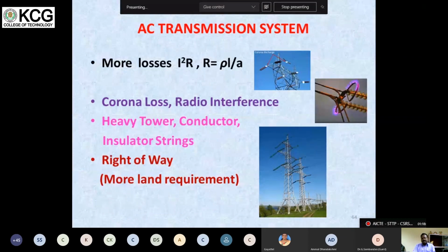Okay, AC transmission lines have some problems, like more losses. They have I squared R loss, resistance loss, and inductance loss also. I squared R is a power loss. Whatever power is generated, when it reaches the load center it incurs losses: technical loss and commercial loss. Technical loss is I squared R loss. R is rho L by A. The loss increases with the resistivity of the conductor, and it also increases with the length of the conductor.